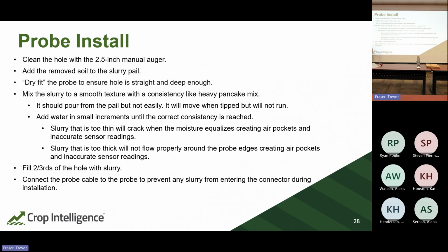Also, when installing the probe, always install the probe cable first, because that makes sure that there is no dirt, debris, or slurry mix getting up into the connector when you insert it down into the hole with the slurry. The slurry can bubble up and the air pockets coming up will push slurry up. If that gets into the connector, it may not allow the connection to be seated properly, and then you have a probe that's not going to read properly. And the connector does click into place. You probably can't hear it from here, but make sure it's all the way on.